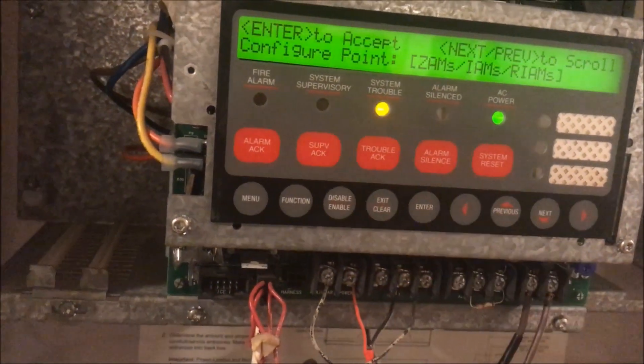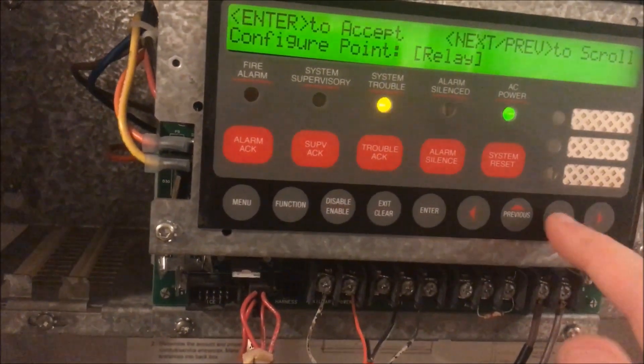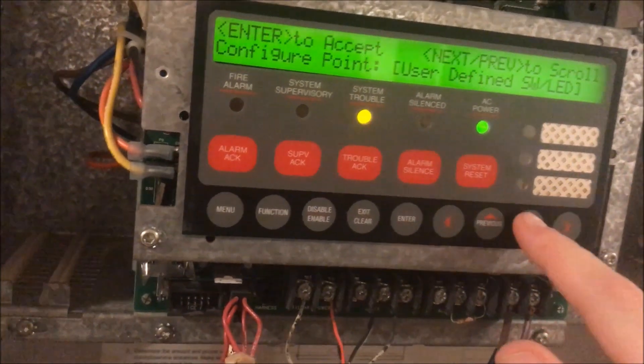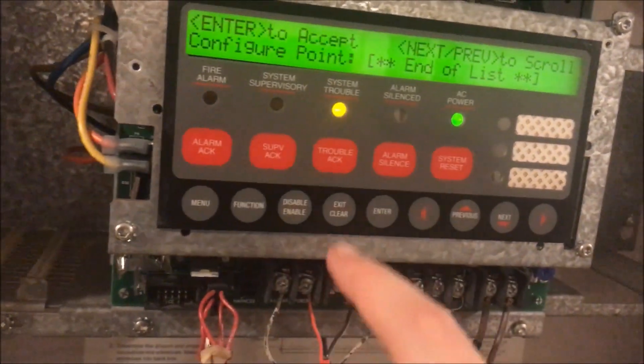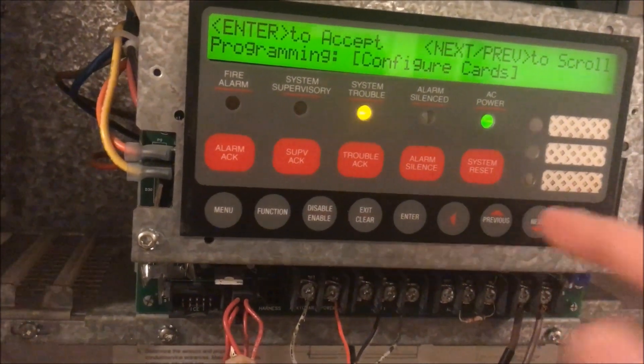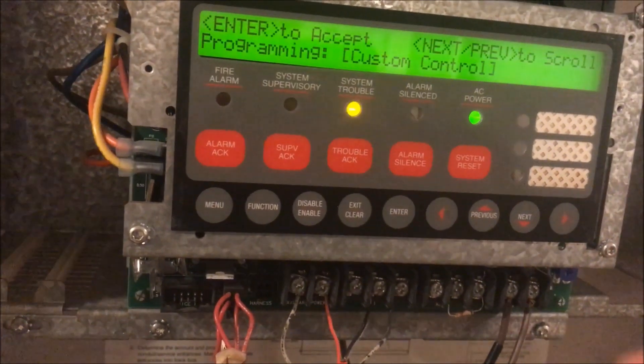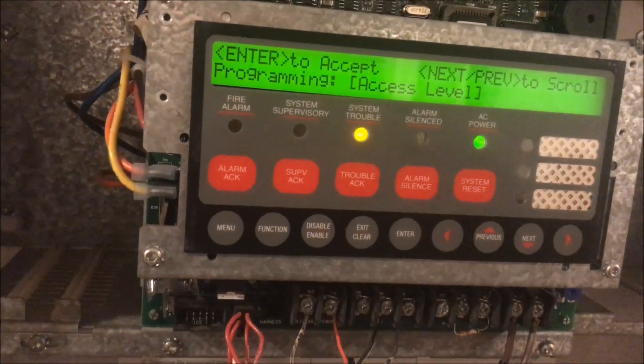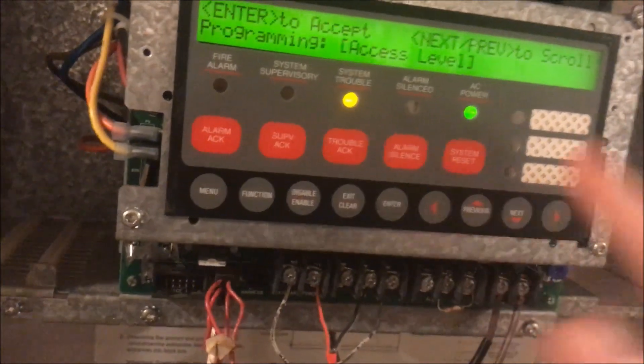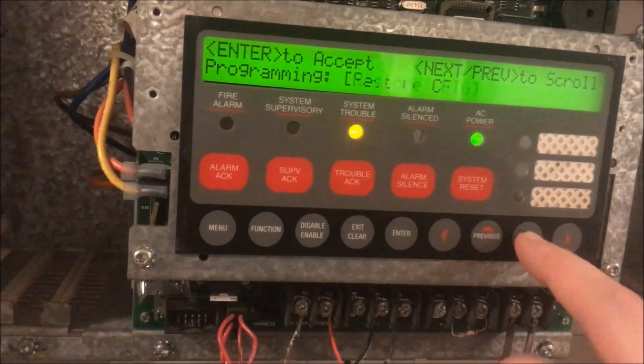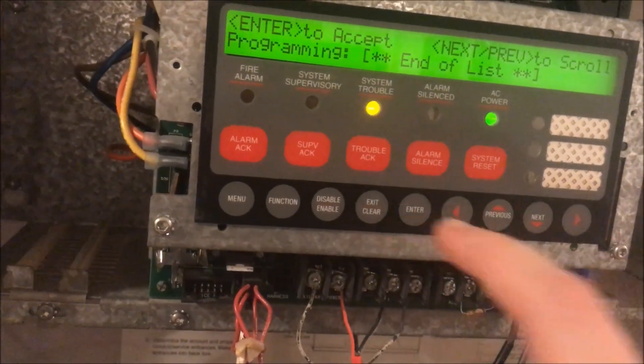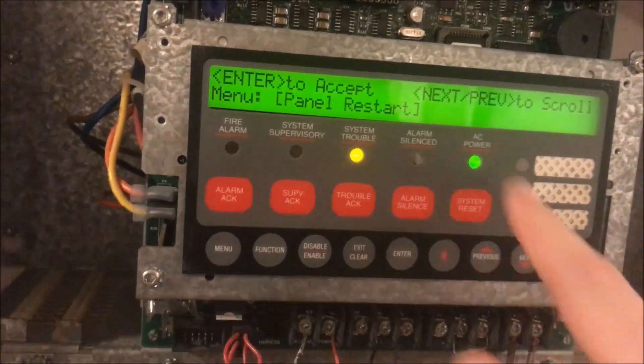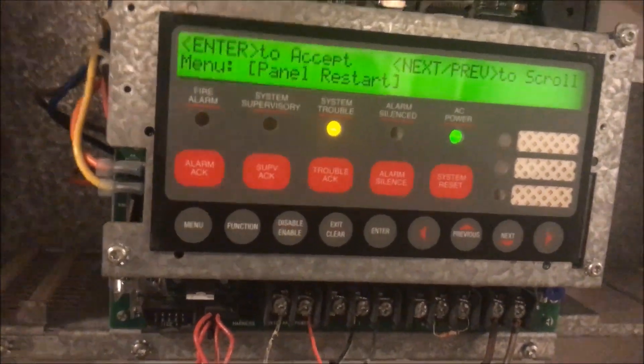After a cold start you'll need to input the date and time again. Other level four features include: viewing your relays and NACs, user-defined LEDs, configuring your network cards, system options, custom control (very application-specific, not something hobbyists typically touch), changing access levels and passwords, and restoring or saving configurations. Along with programming, you can also upload or download software from a computer and view reports.